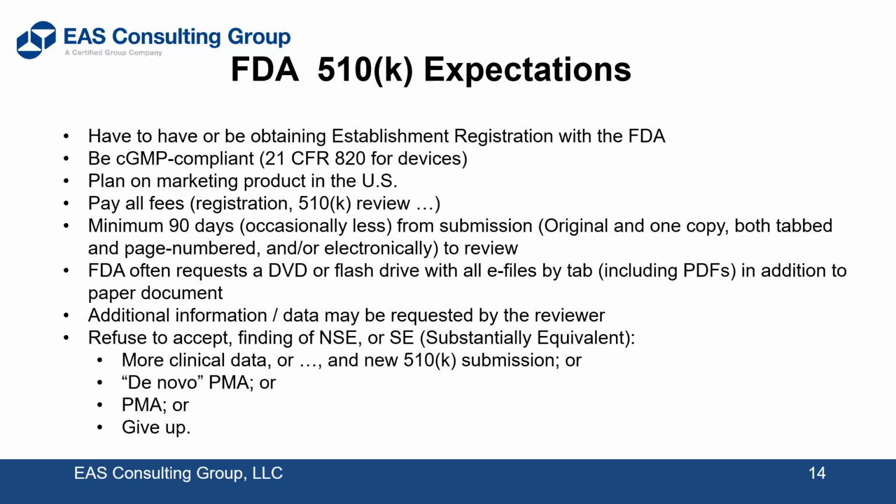If they say non-substantially equivalent, you may end up having to go the clinical route and still be a 510K. You may have to go the de novo route, or you may have to go to a pure PMA route, or you may just pull the whole product as being too costly or involved with insufficient return. It's up to you.